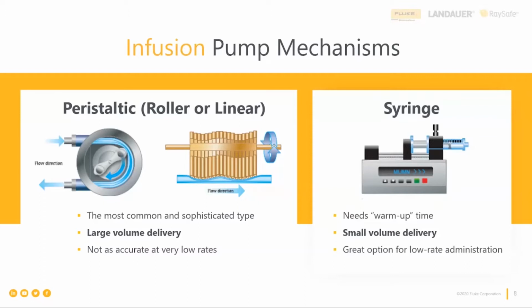Based on that classification, we decided to divide the most widely used infusion pump mechanisms into two bigger groups as well. Those will be the roller and linear peristaltic mechanisms and syringe mechanisms. And the reason why we're specifically pointing out those two different types of mechanisms in infusion devices is because each of them has different points of probable failure, and we'll talk in much more detail about this in a few minutes. And the function of each of those mechanisms has its own impact on the fluid that is flowing through the infusion tubing, which in turn affects the testing process.